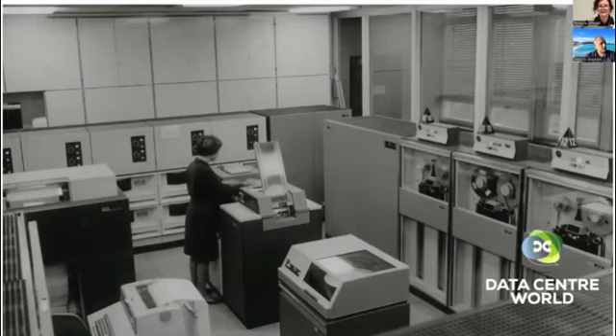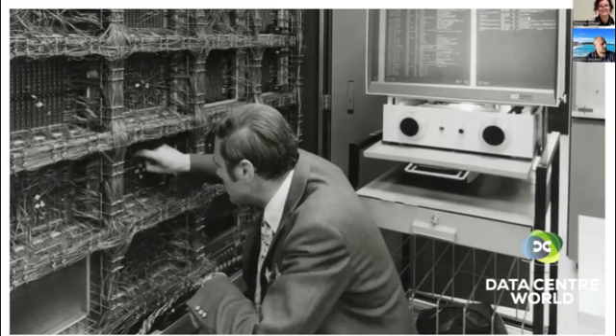And when we talk about humidity and the demand for some humidity percentage in the data center, it actually does not come from the IT equipment, it comes from the demands of the paper and tapes which were in the IT room. But after that, the paper and tapes were gone from the data center, but the requirement for humidity was still there. So people don't know where it comes from. It comes from those first rules for IBM server rooms. This is how it was before. It was too complicated, etc. Everything has changed, but the demands are still there. This is what I wanted to explain about the first innovation, which had an impact on my behavior in data centers.